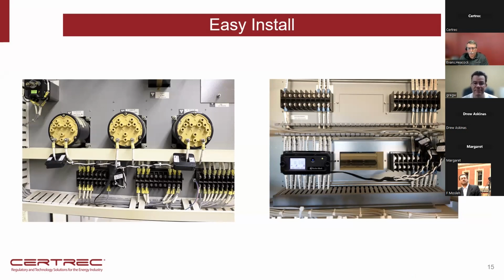And then also you'll describe some of this for the CT circuits, the current circuits, but you have essentially no wiring. That's right. In addition to picking up voltage with our ruggedized pins underneath our device on the front of the panel, during the install we also replace one of the mounting bolts on the Flexi test switch, and we insert one of what we call our smart bolts. It's hollowed out, and we run an insulated tube right through the bolt. It's the same thread as the original bolt, 10-32. So you can still put the old cover back on if you ever need to, but right there through the mounting bolt, we have the insulated cable coming through to the back, and we terminate that with a connector that mates with a 3-phase split core revenue grade CT probe assembly.